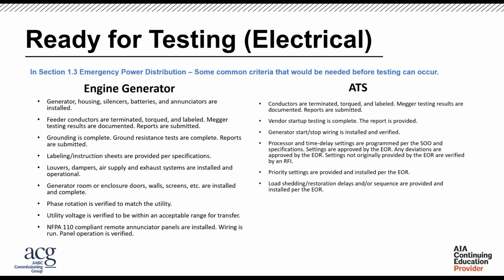So let's talk about ready for testing when it comes to electrical. So engine generator, one of the big things I look at is, hey, is everything installed? Labeling, dampers, had the NFPA 110 test, is it compliant? Has the startup been done? Have we done a load test? Are the remote annunciator panels installed? Phase rotation verified. If this is the indoor test for an engine generator, the HVAC cooling and exhaust are ready. If it's a fuel oil system, is that connected? So one of the things we want is to test the generator in its final condition.